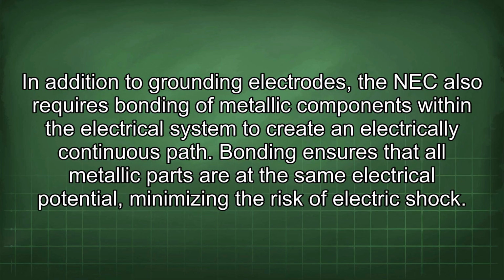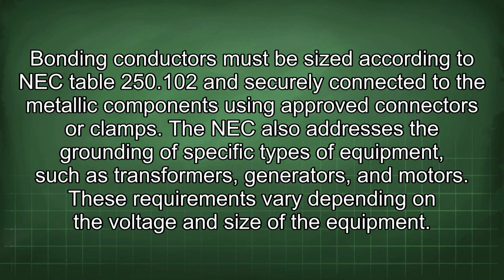In addition to grounding electrodes, the NEC also requires bonding of metallic components within the electrical system to create an electrically continuous path. Bonding ensures that all metallic parts are at the same electrical potential, minimizing the risk of electric shock. Bonding conductors must be sized according to NEC Table 250.102 and securely connected to the metallic components using approved connectors or clamps.